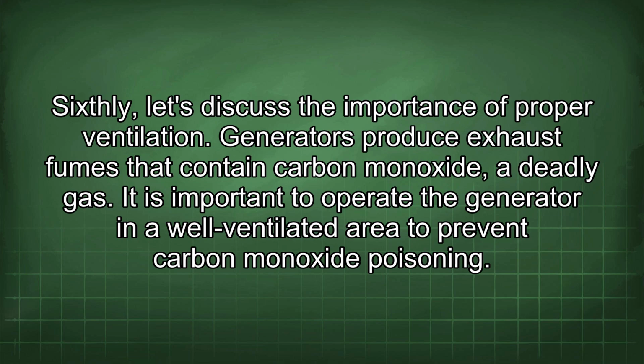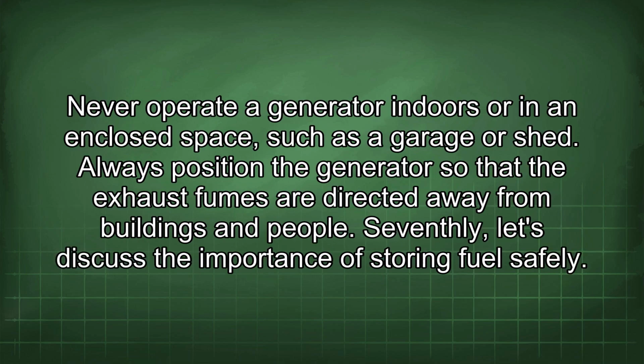Sixthly, let's discuss the importance of proper ventilation. Generators produce exhaust fumes that contain carbon monoxide, a deadly gas. It is important to operate the generator in a well-ventilated area to prevent carbon monoxide poisoning. Never operate a generator indoors or in an enclosed space such as a garage or shed. Always position the generator so that the exhaust fumes are directed away from buildings and people.